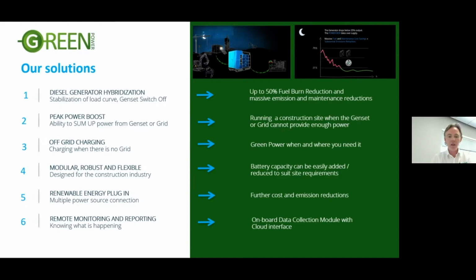By stabilizing the load curve, we reduce fuel consumption per kilowatt of power produced. The peak power boost feature means we can add power from our battery storage onto the maximum power output of a generator to meet higher consumer requirements, without increasing the size of the generator and the associated financial and environmental costs.